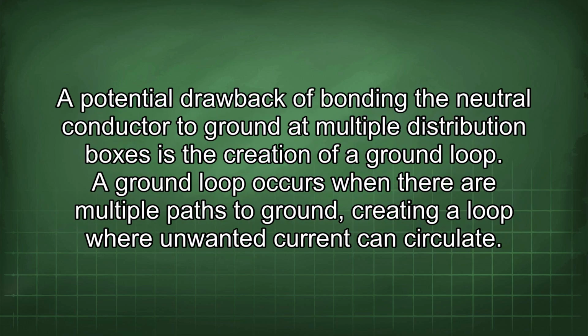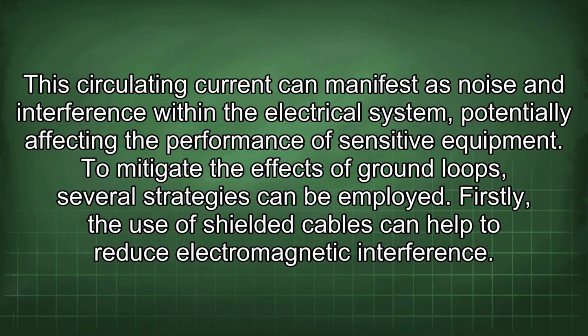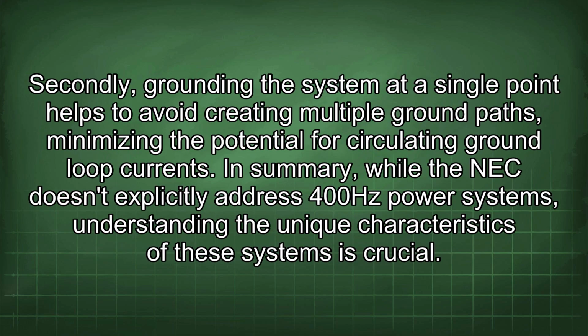A potential drawback of bonding the neutral conductor to ground at multiple distribution boxes is the creation of a ground loop. A ground loop occurs when there are multiple paths to ground, creating a loop where unwanted current can circulate. This circulating current can manifest as noise and interference within the electrical system, potentially affecting the performance of sensitive equipment. To mitigate the effects of ground loops, several strategies can be employed. Firstly, the use of shielded cables can help to reduce electromagnetic interference. Secondly, grounding the system at a single point helps to avoid creating multiple ground paths, minimizing the potential for circulating ground loop currents.